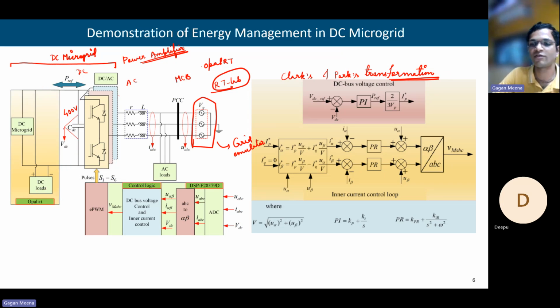And for that, we need a control system that will ensure that whenever there is some deviation, the power has to flow accordingly. For that, we need to track this voltage VDC, this DC link voltage, and the current between the two grids, and also track this PCC voltage. So UABC, IABC - these are the three sinusoidal three-phase current and voltage signals.